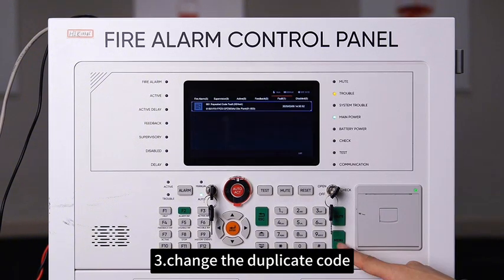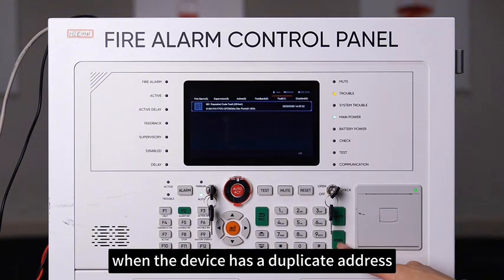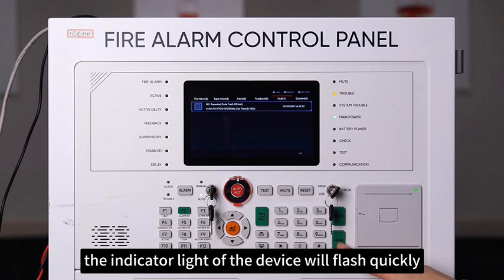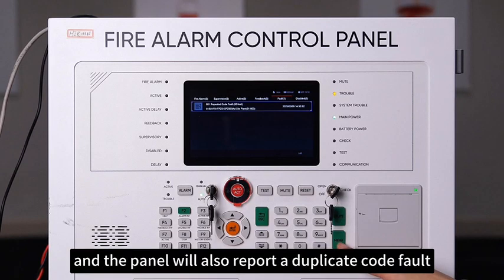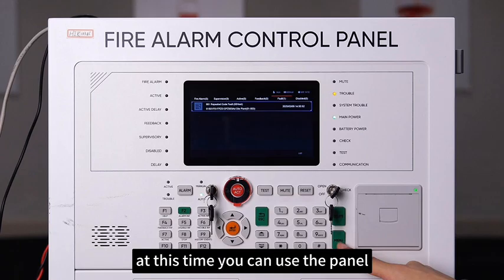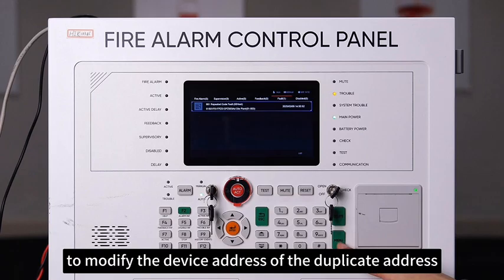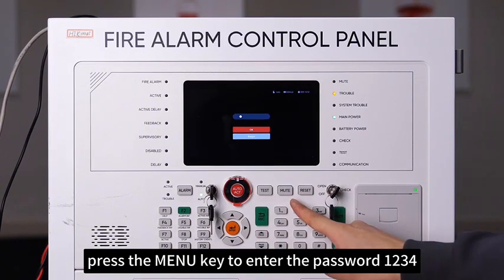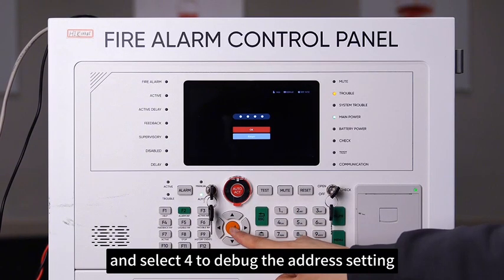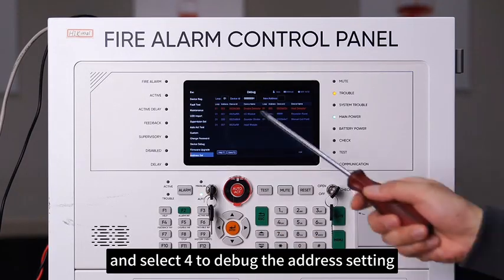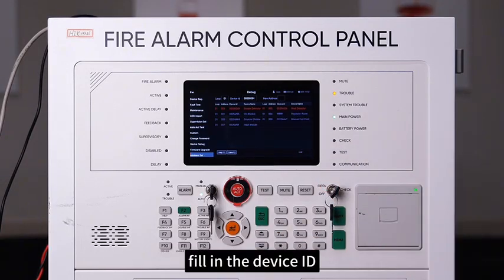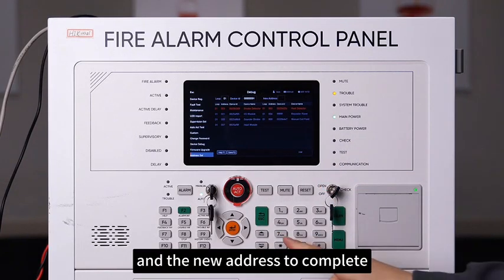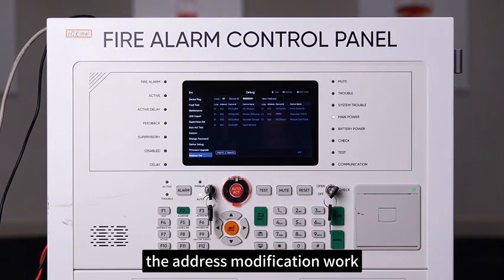Third, change the duplicate code. When the device has a duplicate address, the indicator light of the device will flash quickly and the panel will also report a duplicate code fault. At this time, you can use the panel to modify the device address of the duplicate address. Press the menu key to enter the password 1234 and select 4 to debug the address setting. Fill in the device ID to be modified and the new address to complete the address modification work.